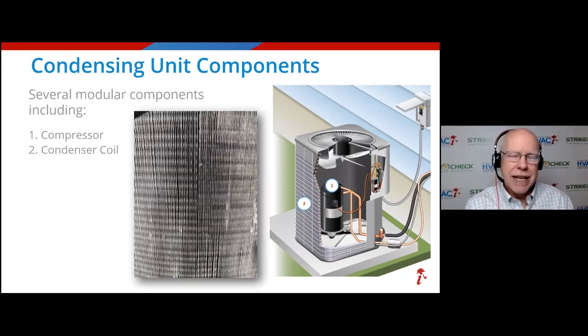I'm not going to have the time to get into too many damages here, but you can imagine these are easily damaged. Number one cause of loss, especially for adjusters, is hail. We have a whole hail class if you want to learn more about that. But anyway, we now have this great amount of surface area of good conducting metals, aluminum and copper, and that is what we need for this next step. I'll tell you more about that as we go. So that's the makeup of the condenser coil and what's going on with the refrigerant in the condenser.